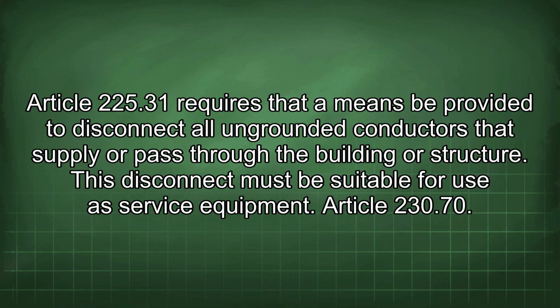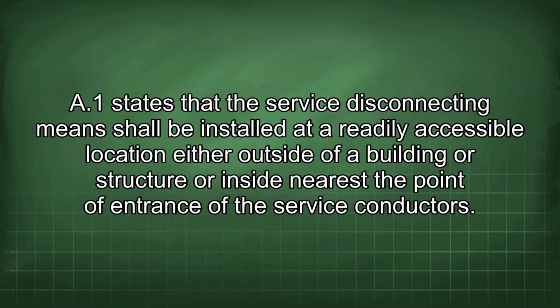Article 225.31 requires that a means be provided to disconnect all ungrounded conductors that supply or pass through the building or structure. This disconnect must be suitable for use as service equipment. Article 230.70(A)(1) states that the service disconnecting means shall be installed at a readily accessible location either outside of a building or structure or inside nearest the point of entrance of the service conductors.